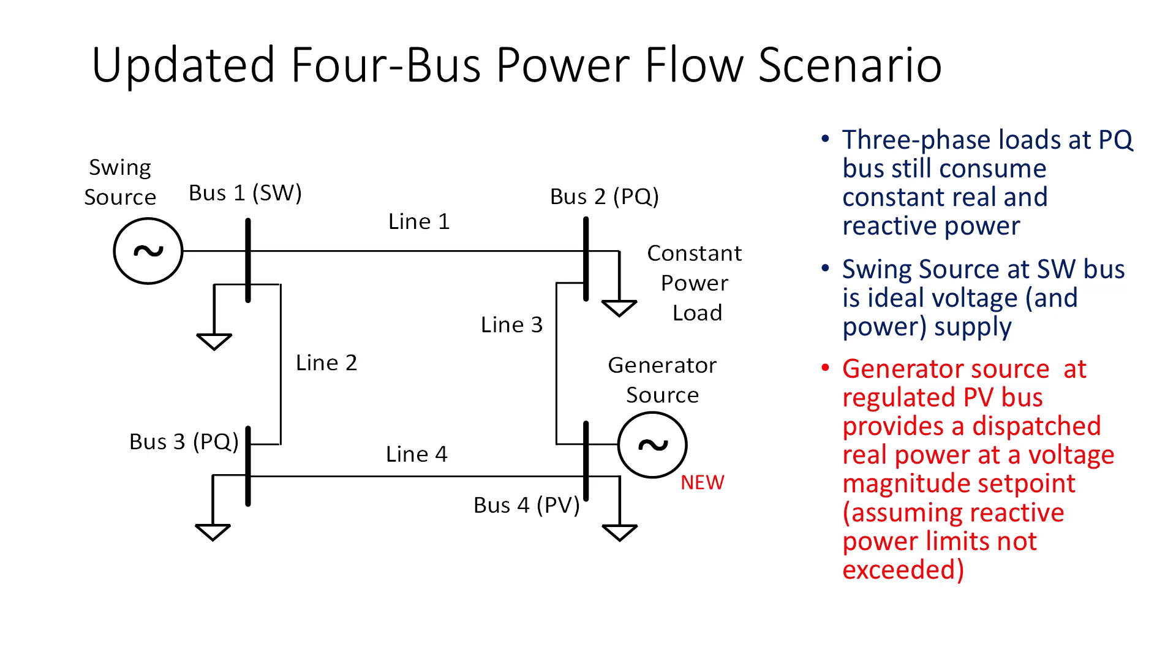The next step in developing this PowerFlow program is to add the capability of modeling generation sources other than the swing bus. A generation source is assumed to be dispatched at a fixed real power injection. The generation source also maintains a constant bus voltage by adjusting its reactive power injection. This generation bus will be referred to in the data set as a PV bus. Note that load buses are PQ buses, and the swing bus is denoted by SW. In this presentation, we will use the 4-Bus system shown here for our coding examples. However, in the final code, we will be able to handle larger bus systems.